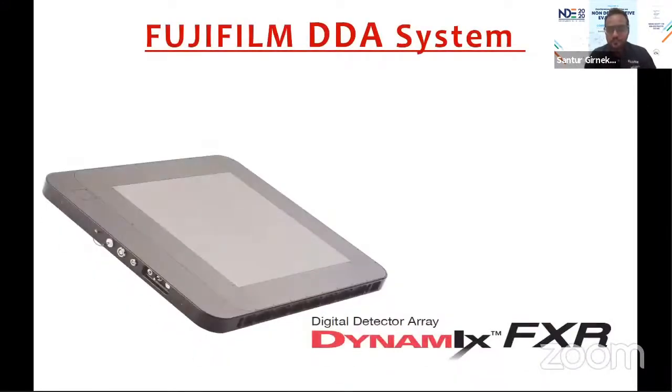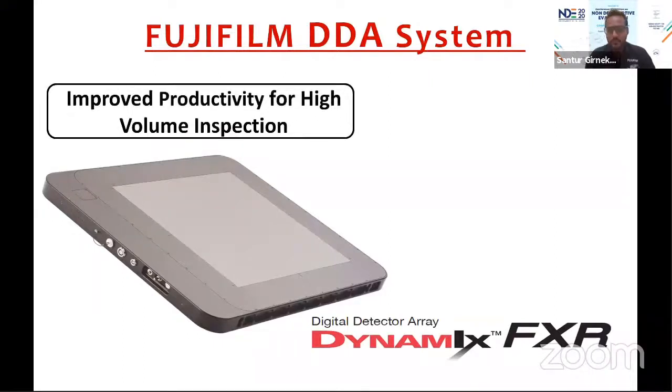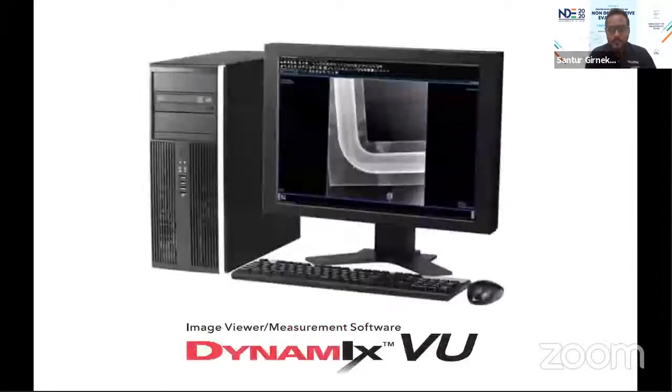The other one is the Fujifilm DDA system, which is the biggest size panel. This is DynamIx FXR, specifically for high productivity and high volume inspection. The pixel pitch is about 100 micron and it is capable of an energy level of 15 MeV, and it has a 16.6 inch large active area. And we have our own image processing software, which is DynamIx VU.